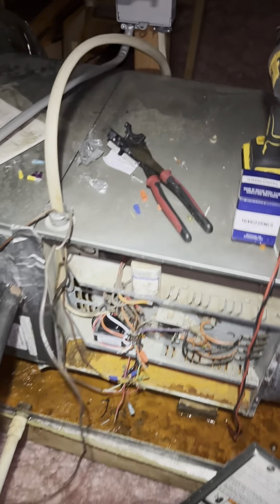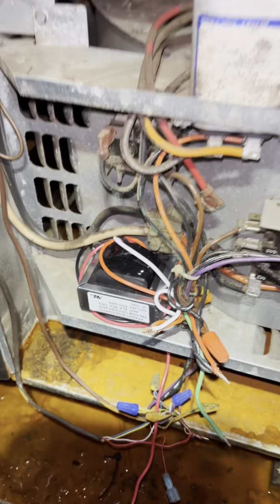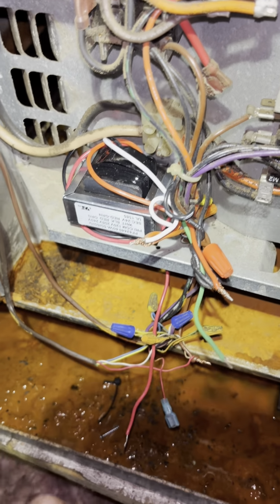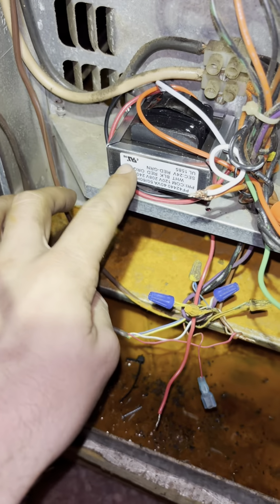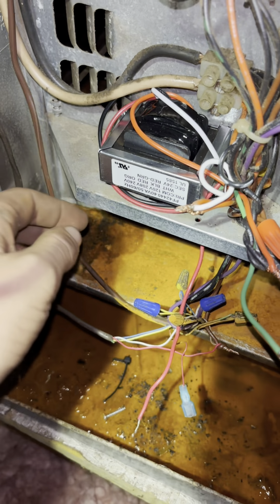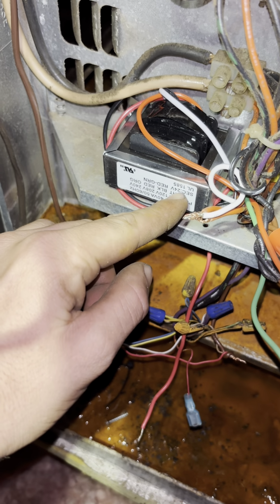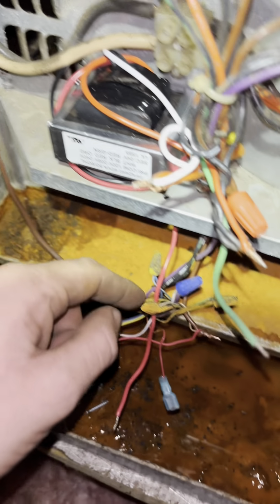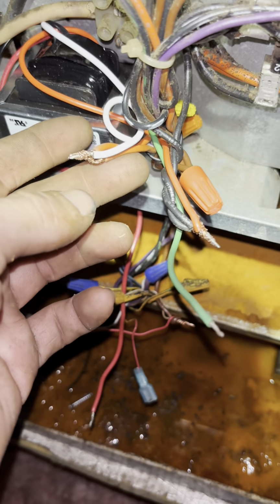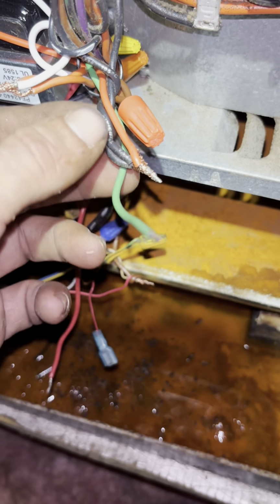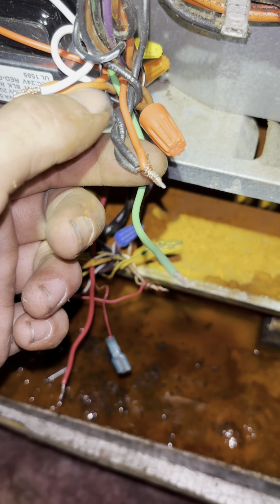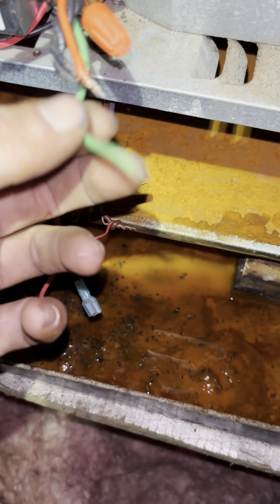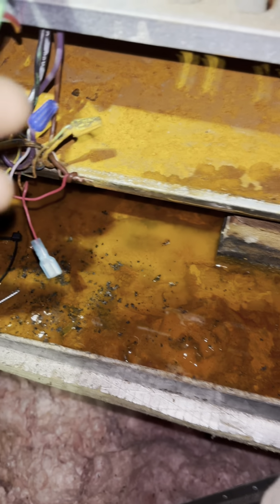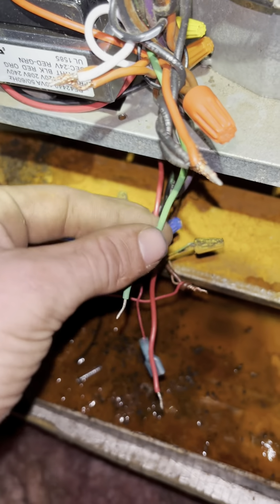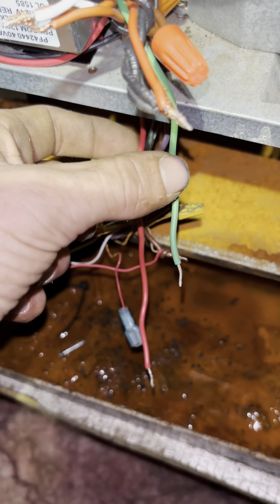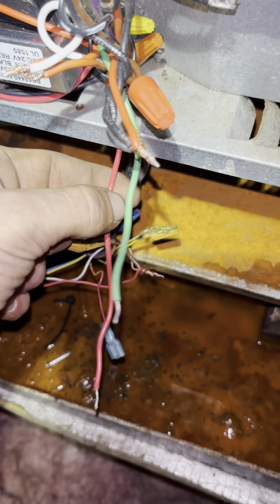All right, guys, I'm up here in the attic. Usually, when the thermostat doesn't work, it's because it's not getting voltage from the transformer, which is right here. If I look right here, it says common is white and orange is your 240 leg. And right here I have white as your common, because I know that orange is going to L2. Orange and black are tied in together because that's your leg. So now coming in is 240 volts, and coming out should be 24 volts between this green and this red. So let's turn it on and see where the voltage is going.